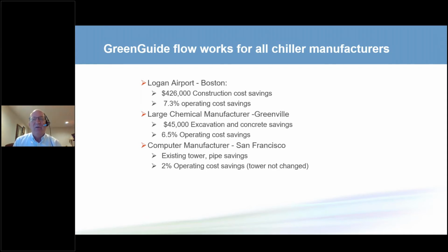There was a large chemical manufacturer in one of the states in the US, and when they reduced their flow rates, they had a large built-up cooling tower. With that cooling tower, not only did they reduce the size of the cooling tower, but it had a concrete sump. And that concrete sump was also able to be reduced. So not only did the cooling tower costs go down, but the cost for the sump went down.